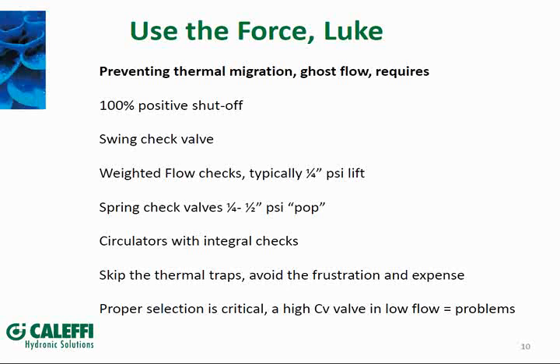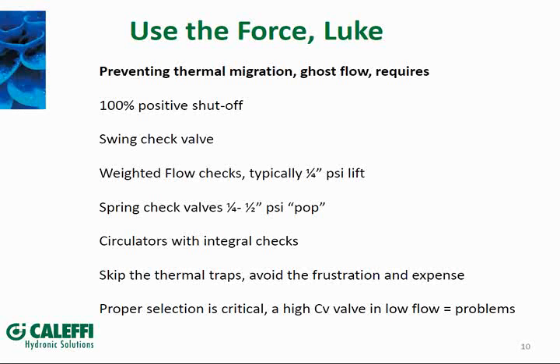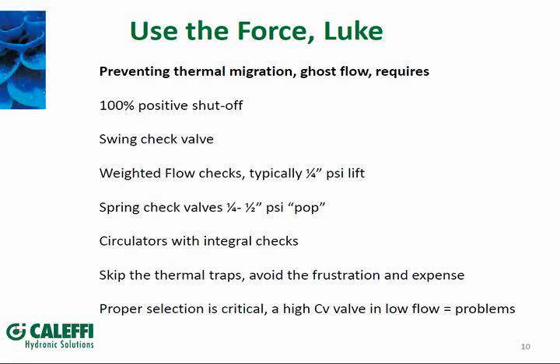In the hydronic industry, we typically look at a couple types. There's the weighted flow check, where the weight of the plug inside closes off flow when the pump stops — that weight is what prevents thermal migration or ghost flow. Spring checks are another way; many circulators now come with spring checks built right into the volute so you don't have to pipe them separately. We also tried thermal traps — piping a loop down to the floor — though I didn't have very good luck with those.